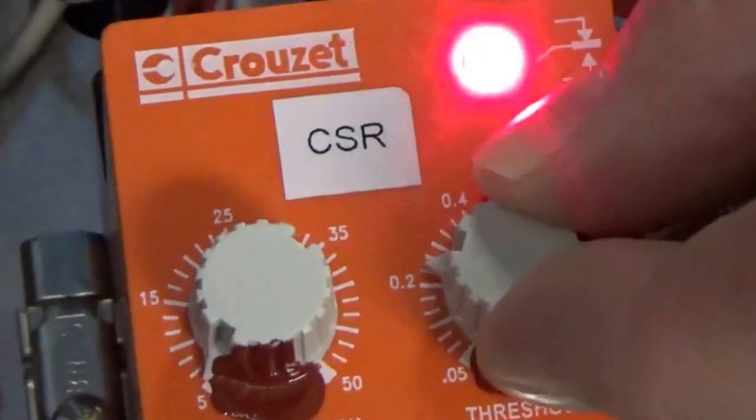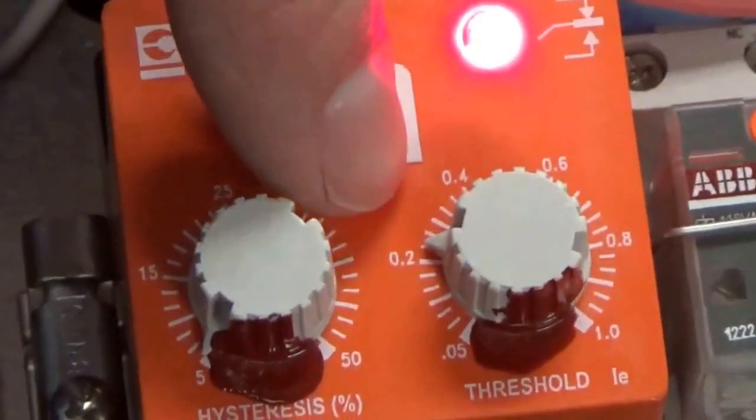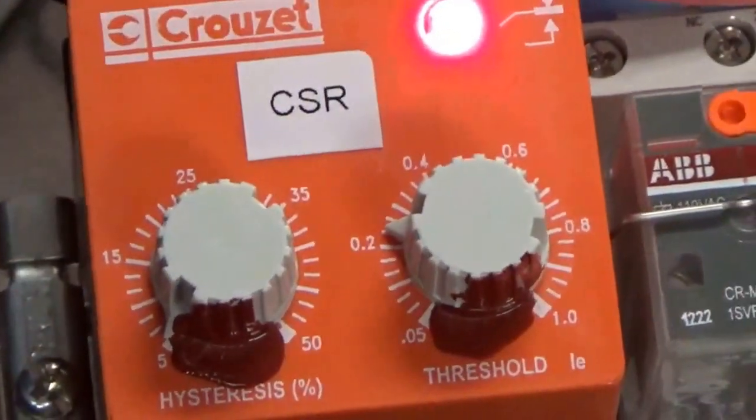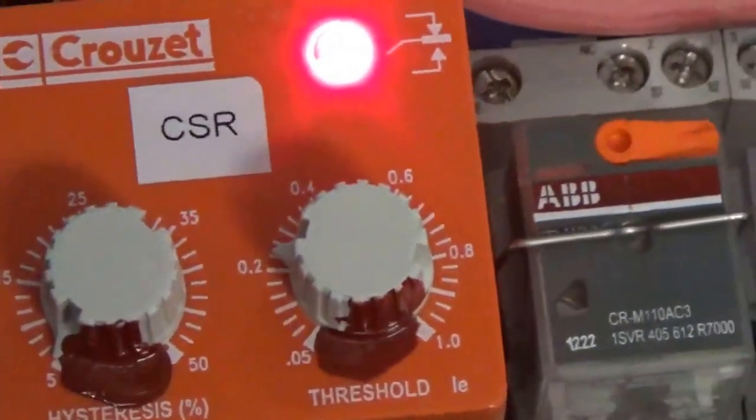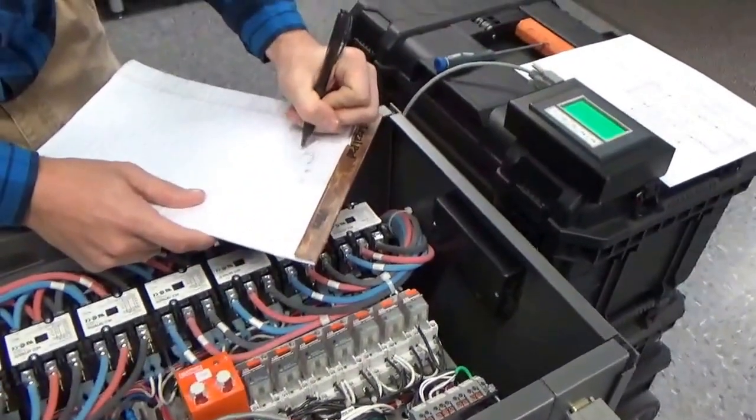Again, toggle it a few times. Make sure you know where that point is. It looks like we're at 0.23. I'm going to turn off control power. I'm going to write that number down. 0.23.